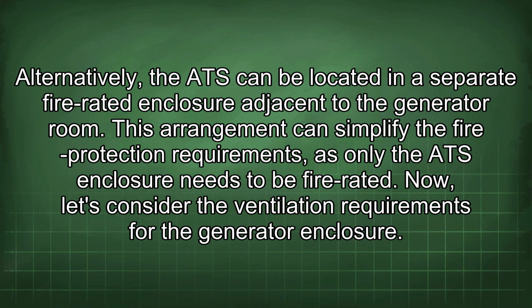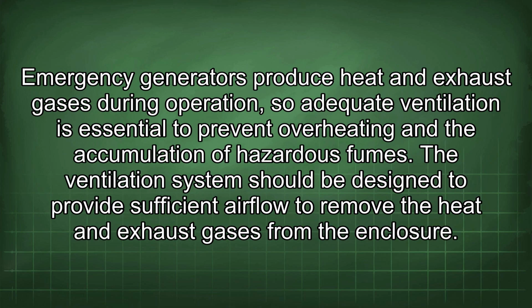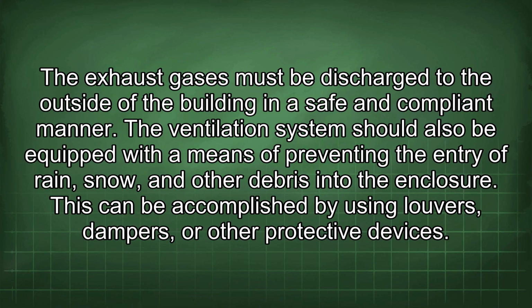Now let's consider the ventilation requirements for the generator enclosure. Emergency generators produce heat and exhaust gases during operation, so adequate ventilation is essential to prevent overheating and the accumulation of hazardous fumes. The ventilation system should be designed to provide sufficient airflow to remove the heat and exhaust gases from the enclosure. The exhaust gases must be discharged to the outside of the building in a safe and compliant manner. The ventilation system should also be equipped with a means of preventing the entry of rain, snow, and other debris into the enclosure. This can be accomplished by using louvers, dampers, or other protective devices.